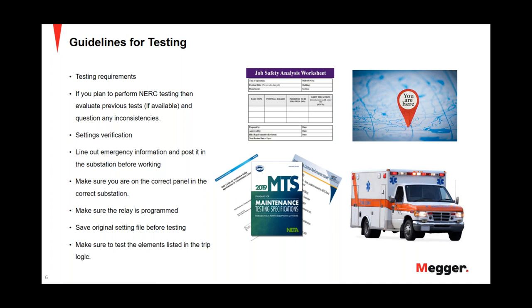The relays were monitoring current and voltage values like they should, and nothing ever tripped — they lucked out. That comes back to the setting verification part: make sure what's actually in the relay is updated and programmed. When we go to substations, make sure you have some type of emergency information available — GPS coordinates of the substation, telephone numbers to local fire departments in those areas. When you're a test technician by yourself going out to location, you want to make sure you have a way to get help if needed.